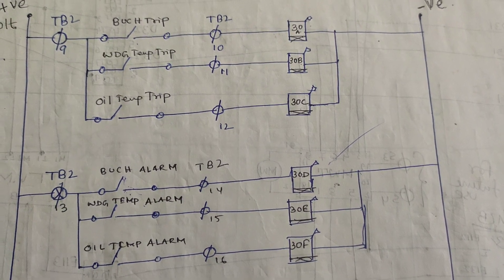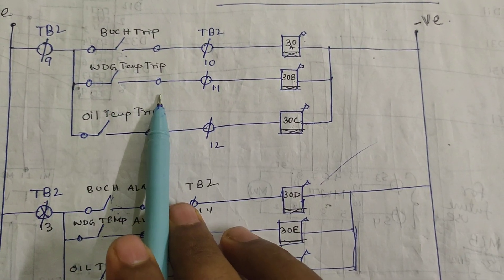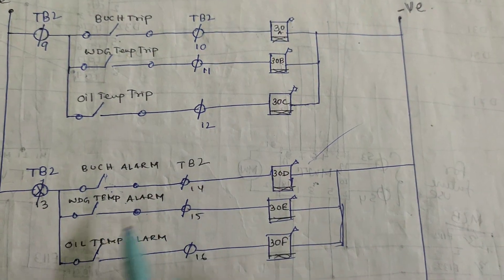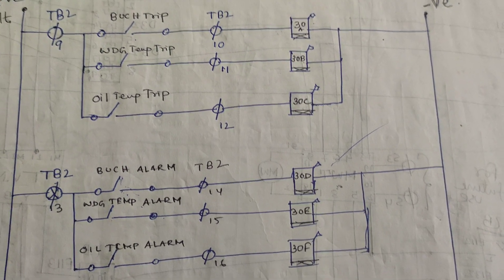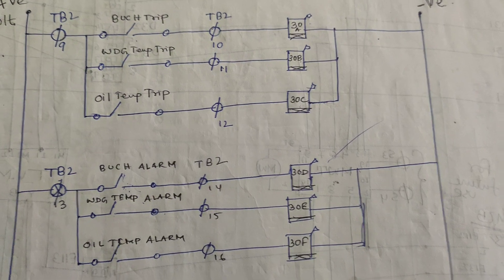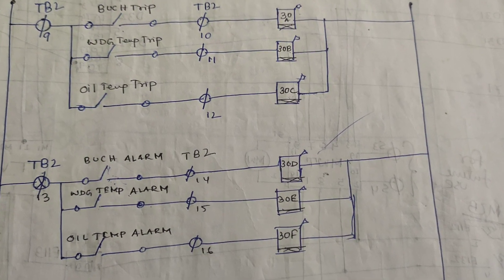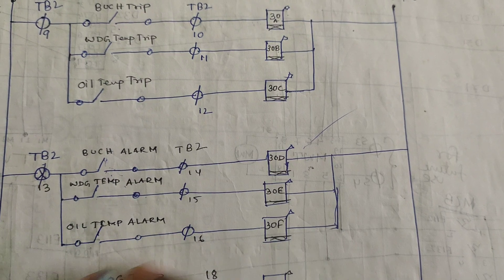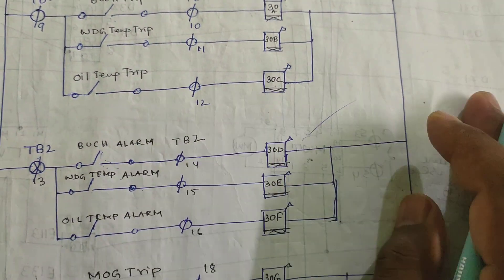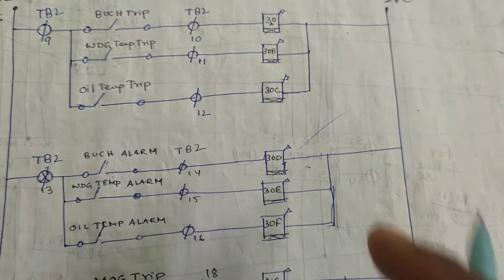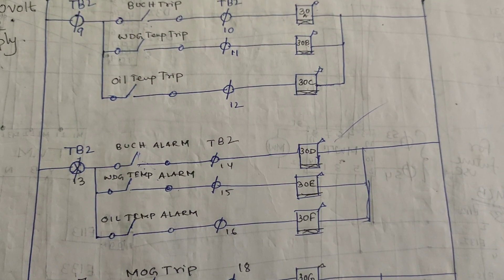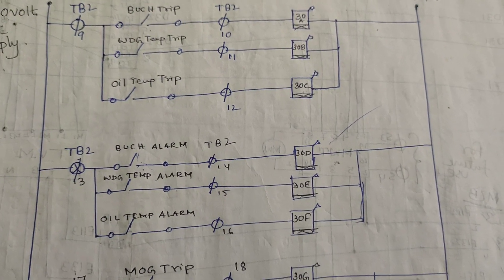The winding temperature trip and alarm work on temperature differences. If winding temperature reaches 75°C, the alarm activates; if it reaches 85°C, the trip activates — indicating something wrong inside the transformer. For oil temperature: the alarm typically activates at 85°C and the trip at 95°C. These are predefined values that vary by manufacturer.